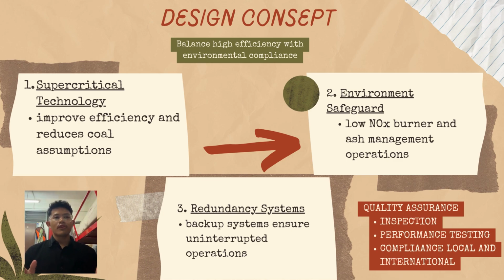Okay, so the design concept of Jimah power plant reflects a balance between maximizing operational efficiency and maintaining reliability. The first design concept is supercritical technology for efficiency. Jimah Power employs supercritical and ultra-supercritical steam technology, a state-of-the-art system in a coal-fired power plant. They use high pressure and temperature, so the steam is generated at extremely high pressure and temperature, typically above 540 degrees Celsius and 24 MPa, which improves the thermodynamic efficiency of the plant.